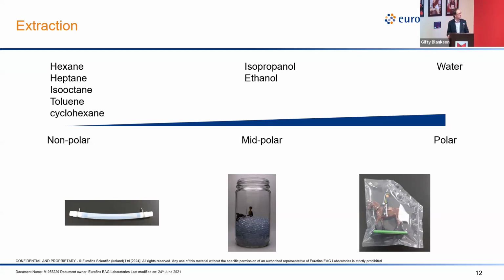So the other thing we do is we cover the range of solubilities. Like dissolves like, and we want to see everything that's coming out of the device. So we use a polar, a non-polar, and a mid-polar. Polar, you pretty much have one option. You have water, right? And for a medical device, it better be able to survive water, otherwise we're going to have a problem. Mid-polar, isopropanol and ethanol are two choices. There are some more esoteric ones, but those are the pretty common ones.